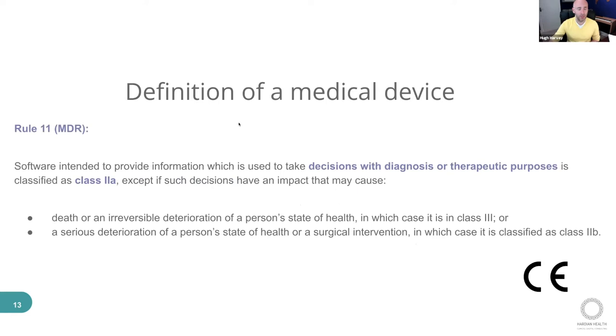If you want to get technical, under Rule 11 of medical device regulations, it specifically states that any software involved with decisions around diagnosis or therapeutic purposes is automatically class 2A, but it can actually be class 3 if it's possible to kill a patient by making the wrong assumption. So things looking at, for instance, acute stroke, could be class 3, because if you get that wrong the patient can die within 4 or 5 hours. So it's very critical that you get your intended use right, and then you find out what your risk class is based on that intended use.